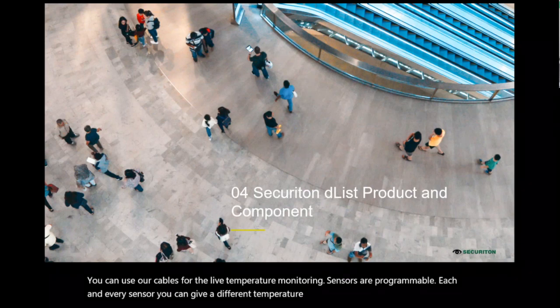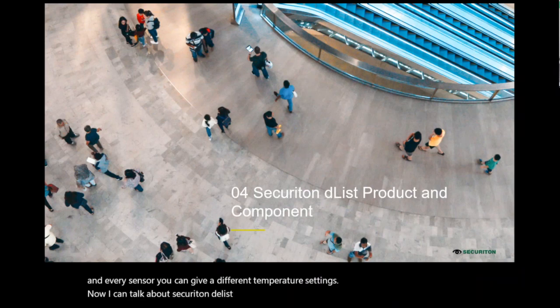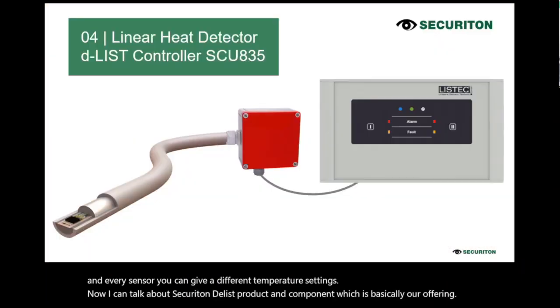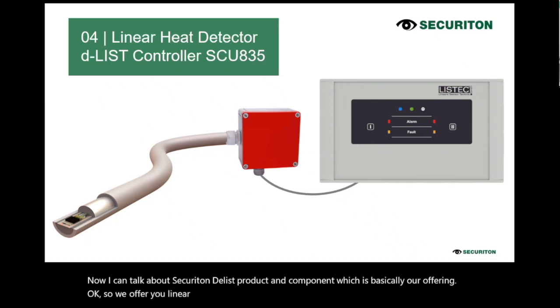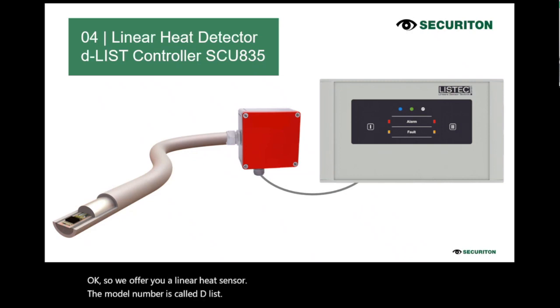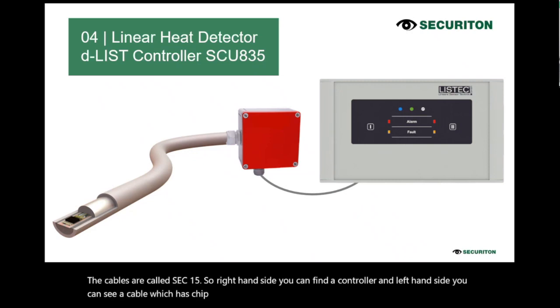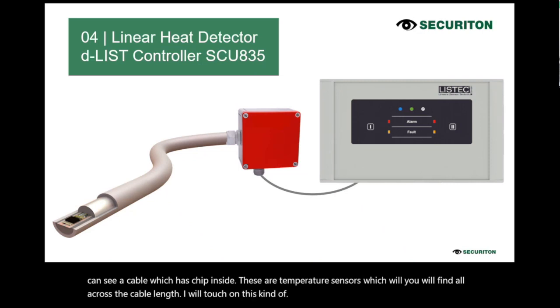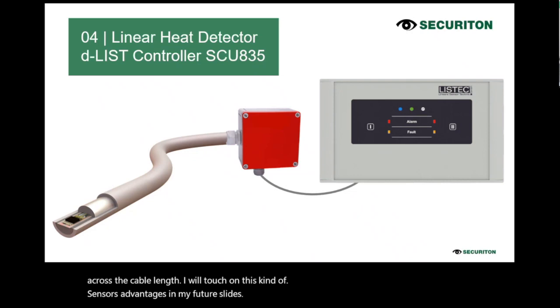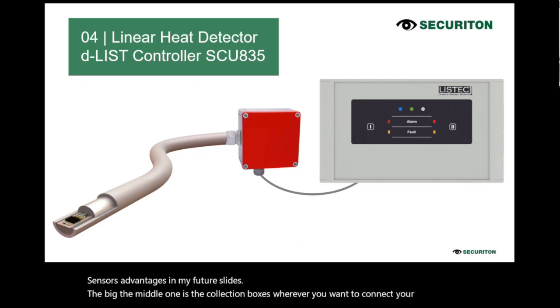Now I can talk about the Securiton dList product and components, which is basically our offering. We offer you a linear heat sensor. The model number is called dList. The cables are called SEC15. On the right hand side you can find a controller, and on the left hand side you can see a cable which has a chip inside. These are temperature sensors which you will find all across the cable length. I will touch on the advantages of these sensors in my future slides. The middle one is the connection boxes. Wherever you want to connect your detection cable with the normal cable, you can use these connection boxes.